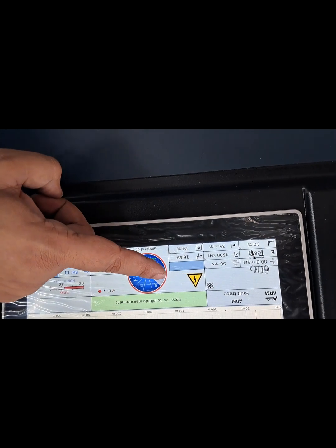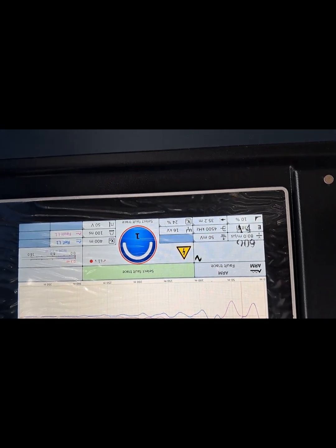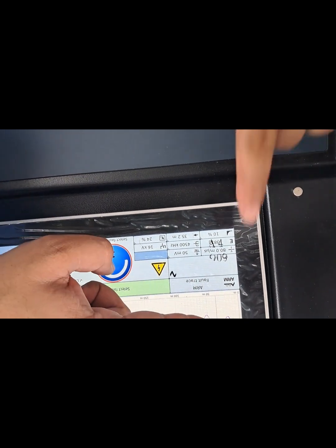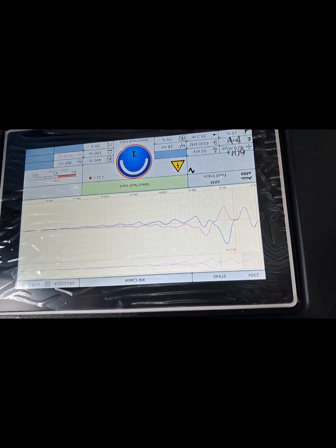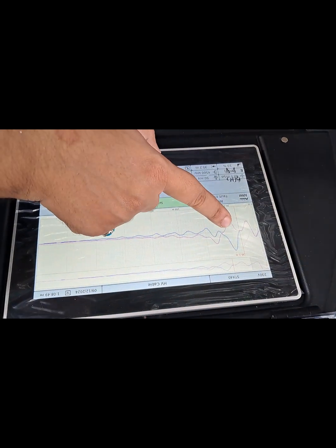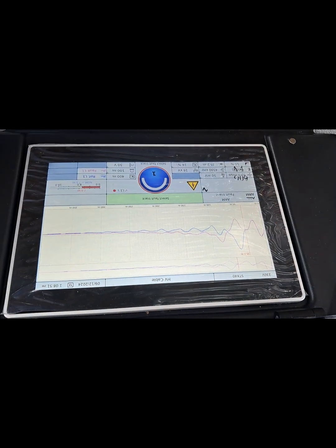Okay, off now, automatically on. 7 kV is there. We just have to give a single shot now. There will be arcing at the fault point. You can listen to the spark. This is your fault graph. It is negative because of the negative peak. Negative peak means arcing filled that gap and it got deviated. This is the fault point at the last end of the cable.